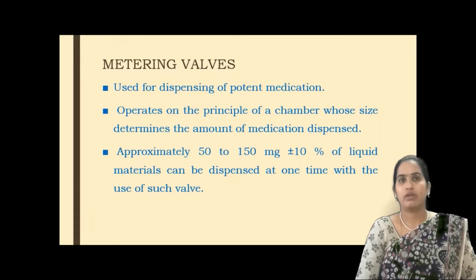These operate on the principle of a chamber, whose size determines the amount of medication dispensed. That means the size of the valve chamber decides the amount of drug to be dispensed. Approximately 50 to 150 milligrams, plus or minus 10%, of liquid materials can be dispensed at one time with the use of such valves.